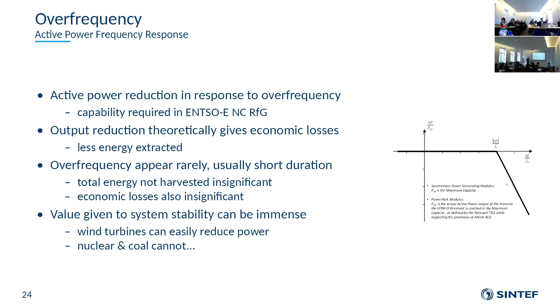But at least this is what wind power can do very well. What's more difficult is the under-frequency part - frequency is too low, we need more power. What do we do with our wind power plant? We need to increase output, and this capability is required by the grid code, at least for larger wind power plants. If you have a single turbine, requirements generally aren't as strict.